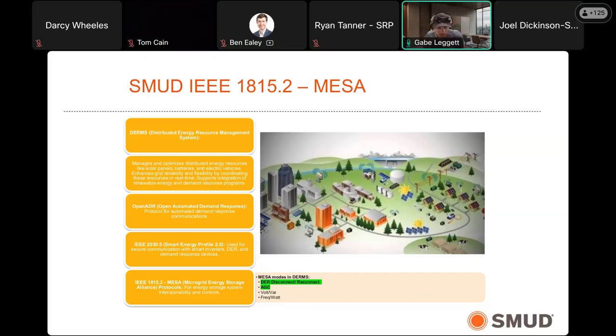Yes, we create an ADMS screen, an advanced distribution management screen. We can get down to, for example, that battery system I was talking about—we can see the six individual containers and information on the power production meter. We can send controls to start or stop, and right now it's operating remotely, so we update the schedule. It's a 24-hour dispatch schedule that we can update daily.